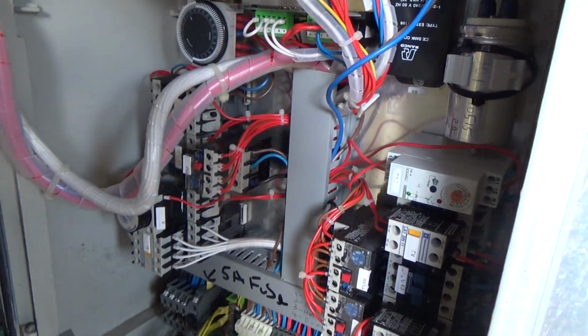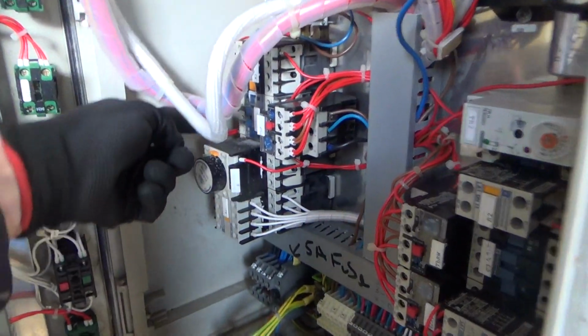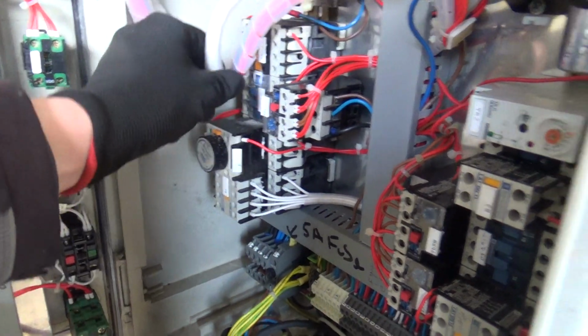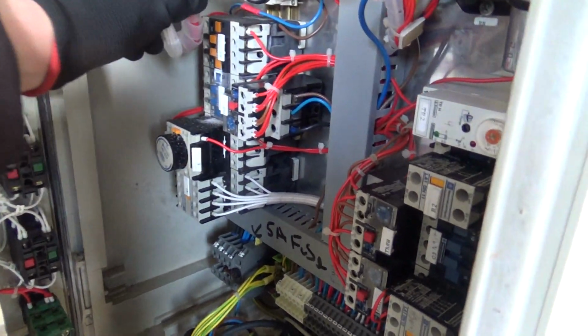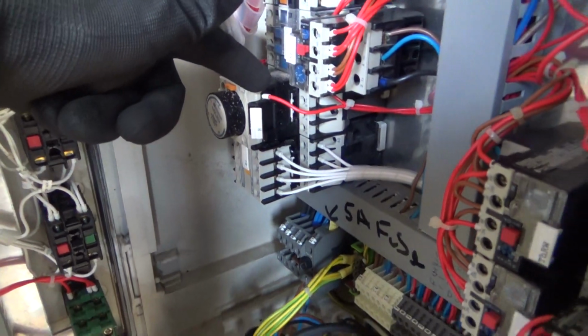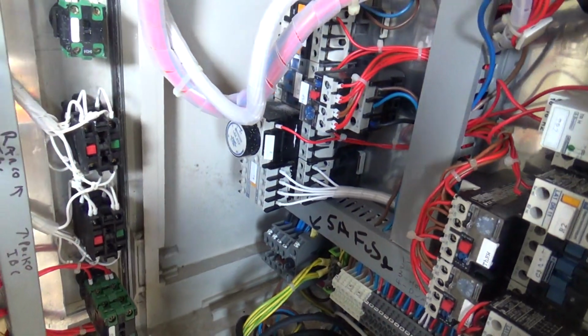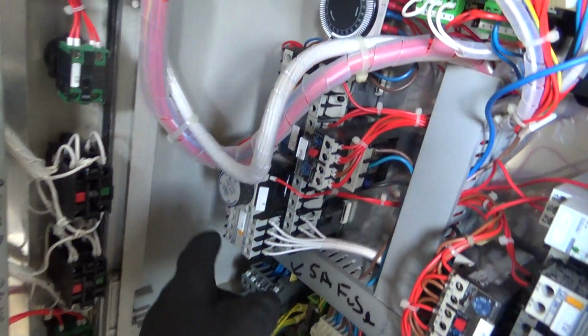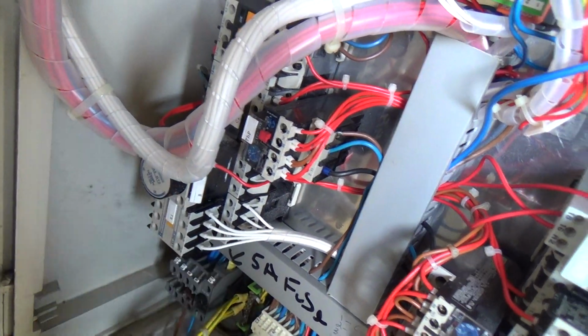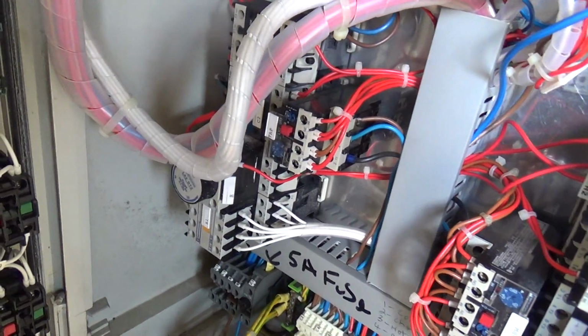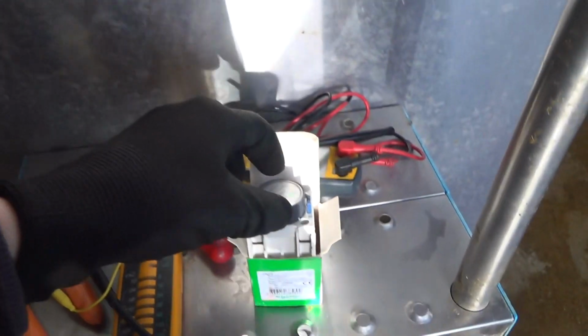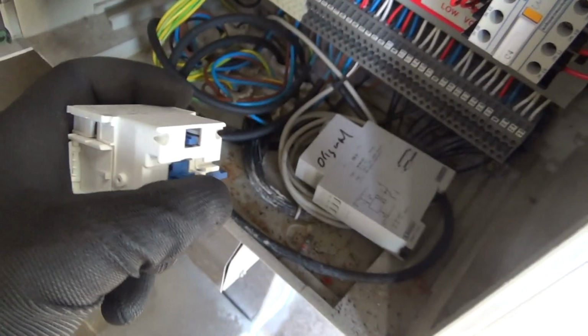We found there's a pneumatic module on top of that contactor there. That's this thing here, which is a 10-second time delay before the second unit kicks in, which is the one that wasn't running this morning. And it's just a little pneumatic timer. That piece there is pulled in.